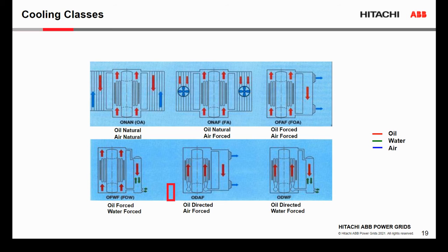with oil forced, we have a solution where we force oil going to the tank, and in this solution, we install the pumps between the cooling system and the tank. The pumps force oil circulation in the transformer. A very similar solution is with the water coolers, where we force oil going to the tank, but the difference is that we use a different type of heat exchanger. So we use water coolers. On one side we have hot oil going in, and then on the other side we have cold water used to dissipate the heat.